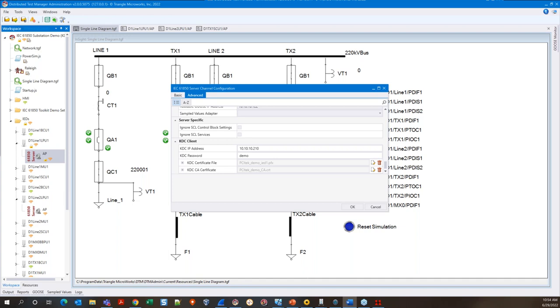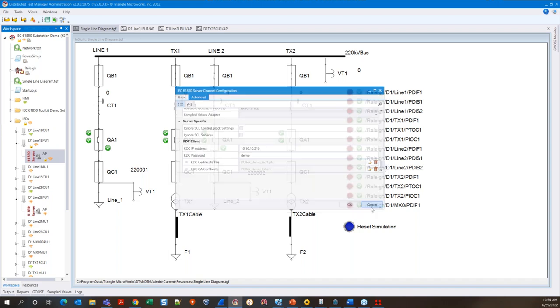Coming over to the Advanced tab, I want to highlight settings that are specific to security. We have indicated the IP address of our key distribution server, or KDC, which Herb talked about — we're using Garibaldi as our KDC server. When our IED performs a pull sequence to retrieve keys from the KDC, this is the address our IED will use to reach out. Below that, we see our passwords field, which allows the IED to access the signed identity certificate and extract the private key. Certificates are seen below — these include the certificate authority, which is shared with the KDC, and the signed identity certificate unique to this IED. Note that these certificates are not contained within the SCD and must be configured in each IED which utilizes authentication and encryption.